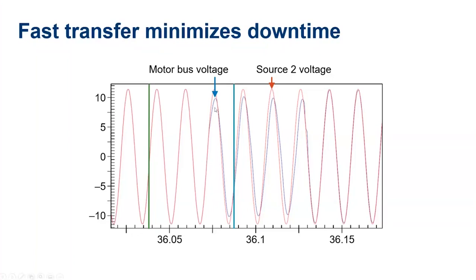When the voltages start to separate, that's where we know the breaker opened, but we still need to wait for a 52A confirmation that the breaker is effectively open. And so when we get the confirmation that the first bus is disconnected, that's where we send the close signal to the other breaker. And again, that signal takes a while to propagate, and the breaker closes. The feeder connects to the bus, and the system goes back to normal operation.